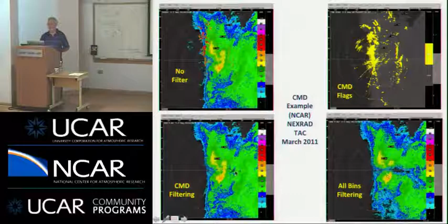And then typically what happened before we had CMD is people would get tired of putting these zones in and they would just say, well, filter everywhere. Let's just filter the whole range. And you can see what can happen here along the area where the velocity is near zero in this particular scan. The clutter filter takes out most things that are near zero in the Doppler spectrum, and so it takes out the power along here. And see, this little storm here got cut in half. So we don't want this, and we do want this, and fortunately, this is what we have most of the time.